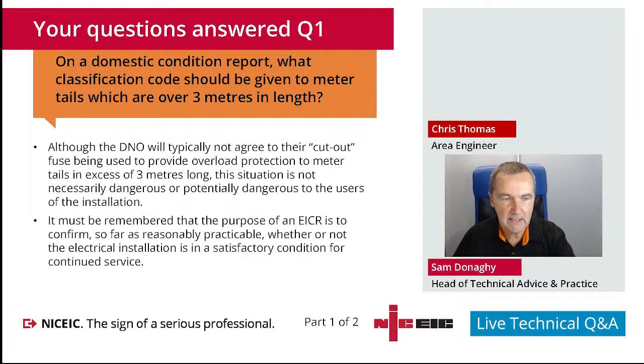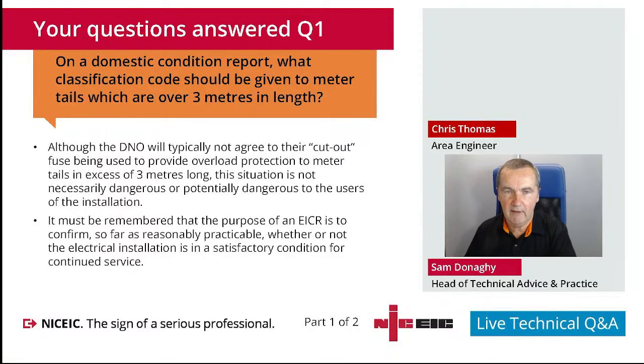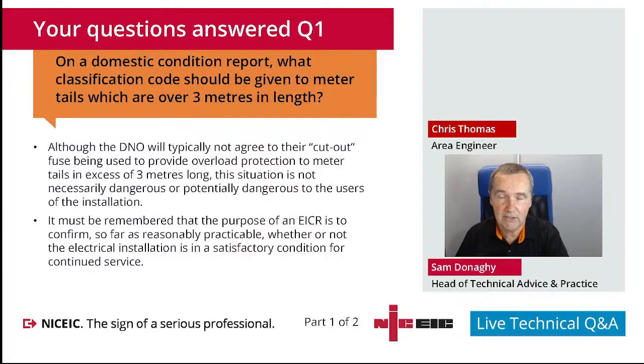The reason being is that it doesn't initially or directly make it unsafe for the users of the installation, which is what the EICR is all about. So as we've put on the slide there, because we know that the DNO will typically not agree to their cut-out fuse being used to provide overload protection to meter tails in excess of 3 metres, it doesn't necessarily mean it's dangerous or potentially dangerous to the users of the installation. We have to remember that the whole purpose of the EICR is to confirm, as far as reasonably practical, whether or not the installation is satisfactory for continued use. So just for the fact that it's over 3 metres wouldn't immediately make it unsafe.